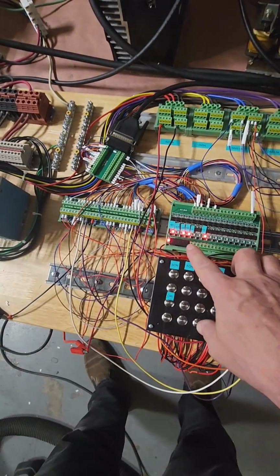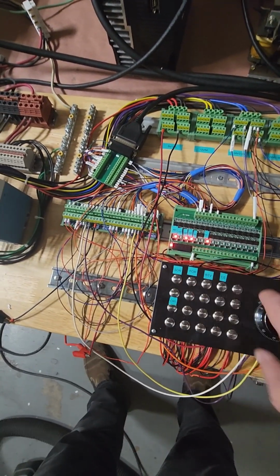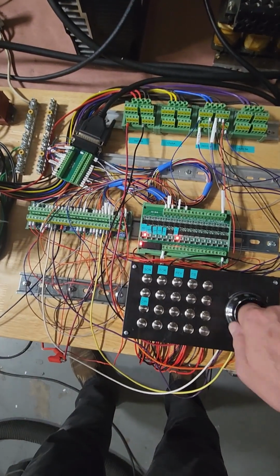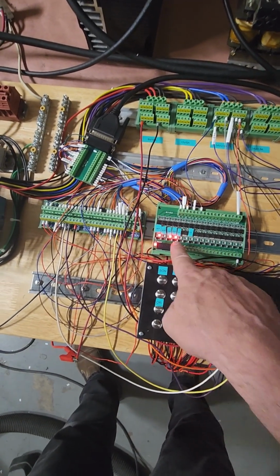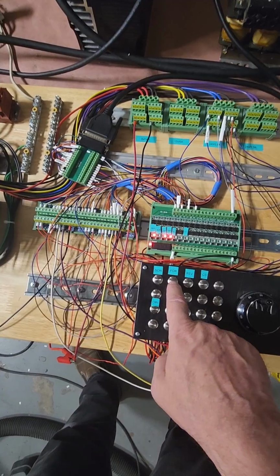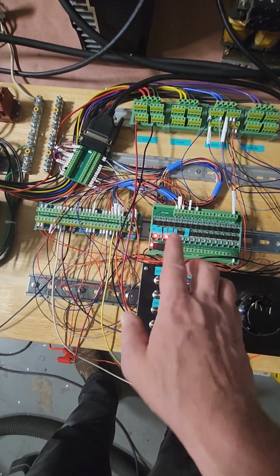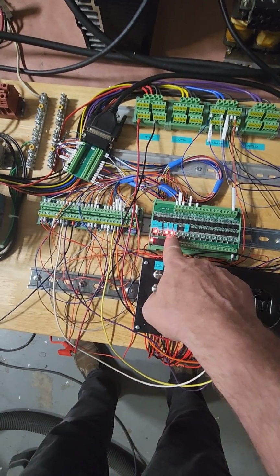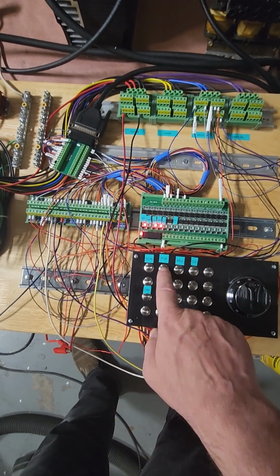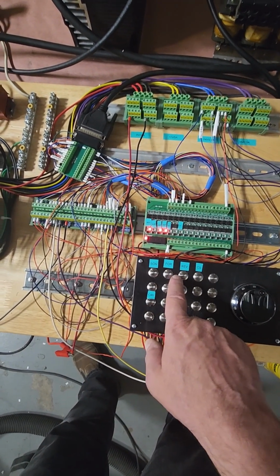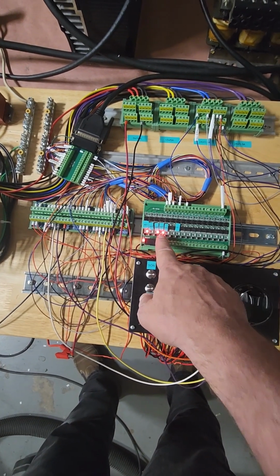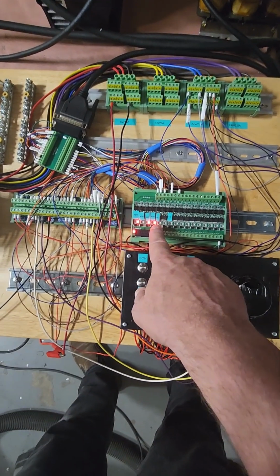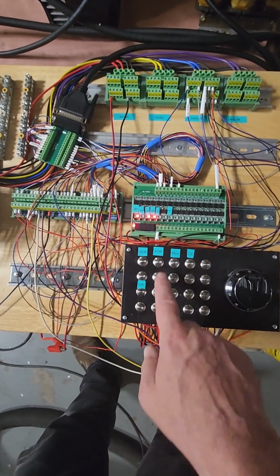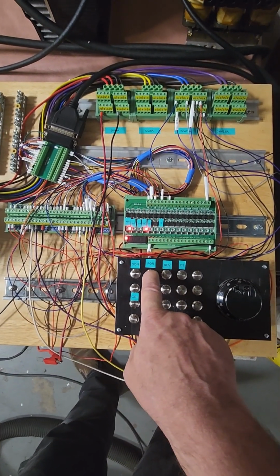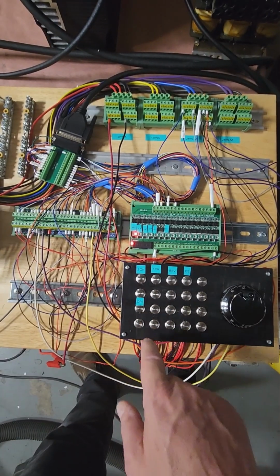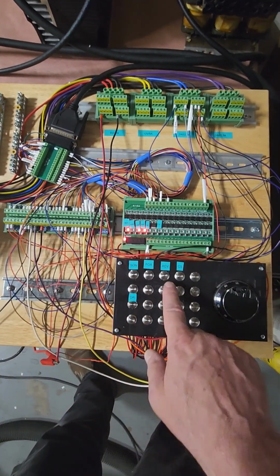One thing I want to show you: when we spin, the ZSP zero speed goes off, obviously, because we're not at zero speed, and also the at-speed indicator turns on. Right now the program speed is 0, so zero speed is on and at-speed is on at 0. But if I run forward or reverse, zero speed will turn off, and at-speed will turn off momentarily until it reaches the speed, then it stays on. Let's see that - see, it's at speed. And again, at speed, 0 and 0 speed, same here.